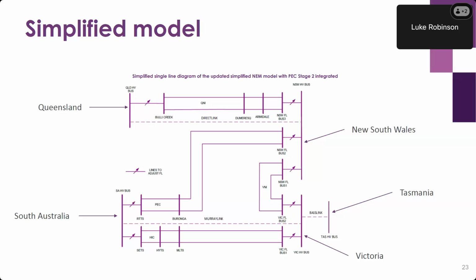Each of the mainland regions is represented by a common high voltage bus, and all the regional generators were assumed to be connected to these regional common buses through appropriate generator transformers. Regional generators were lumped as steam, gas, hydro, wind, and solar with appropriate generic models, such as the alternator, voltage controller, governors, and IBR controllers. We also had the under frequency load shedding and underlying DPV grouped according to their frequency trip bands and connected at the 33 kV distribution level buses, and then connected to common high voltage buses through appropriate transformers. And some areas of interest were still modeled in more detail if it was an area that we were particularly interested in.